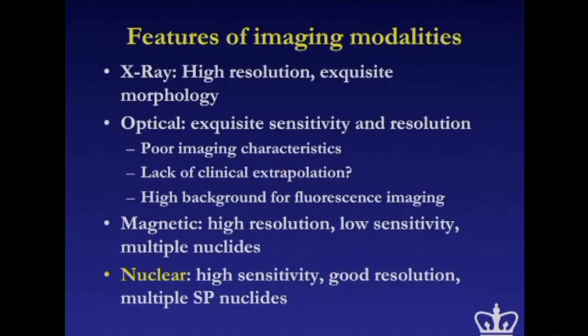And then we have to have enough time also to carry out quality control so that the quality control will assure us that what we are injecting into the human satisfies all the requirements that the FDA and any sensible individual has. So carbon-11 with a half-life of 20 minutes means that we have to carry out the synthesis as well as the quality control. The entire process has to be compressed ideally within an hour from scratch to finish.